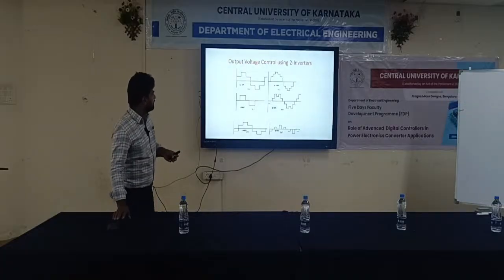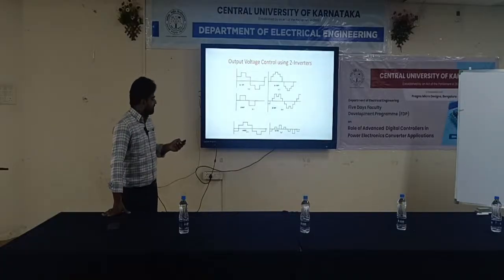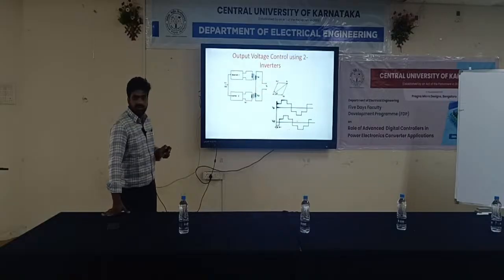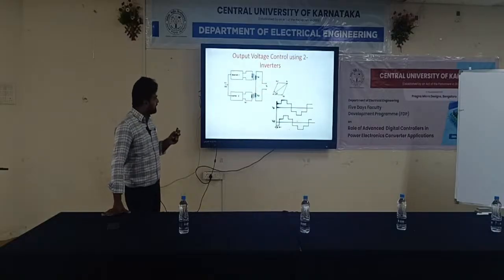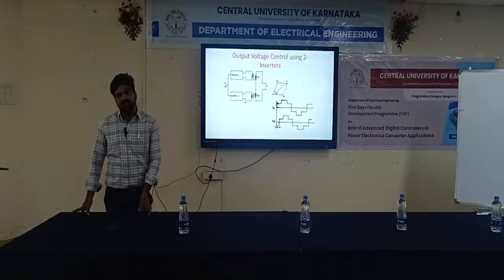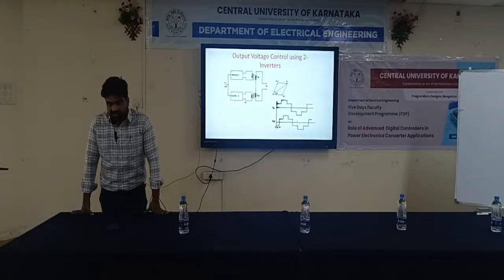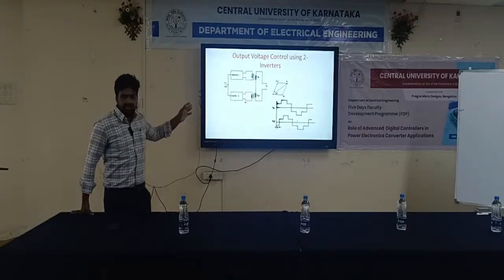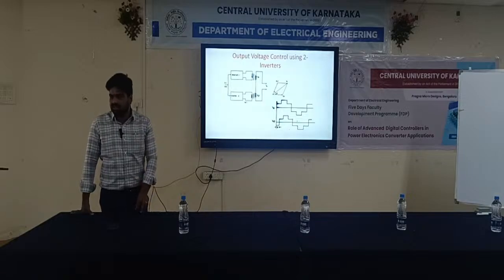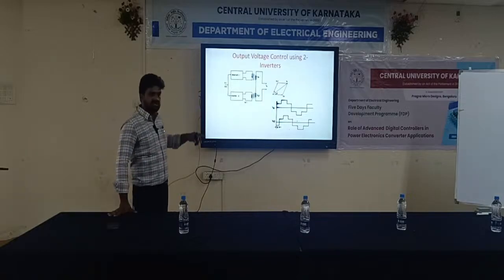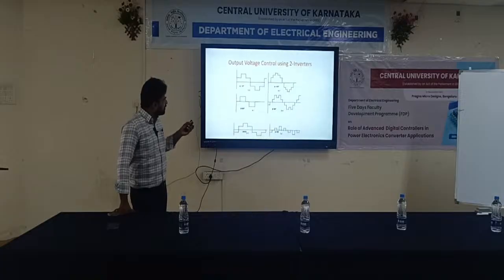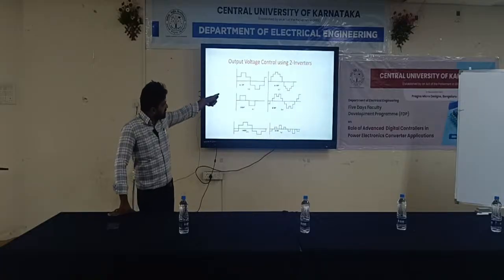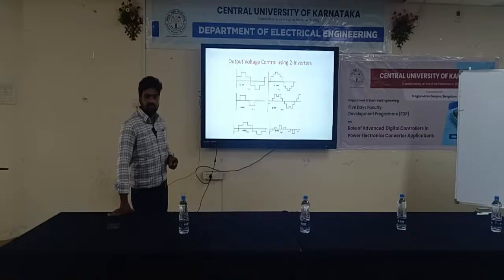So the shift of the transformer should be 30 degrees. How can we get this 30 degree shift? One winding can be star connected and the other delta connected, so the shift between the two windings will be 30 degrees, and the output voltages will sum up and appear such that phi equals 30 degrees.